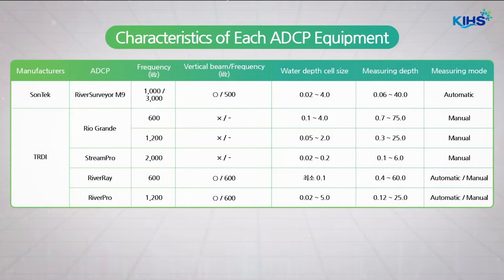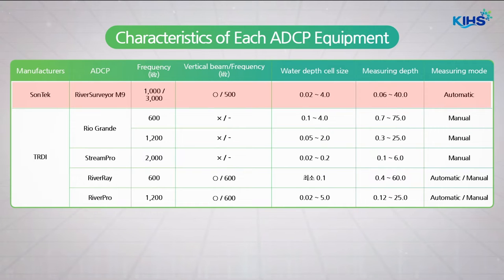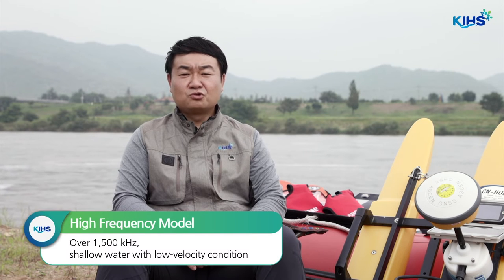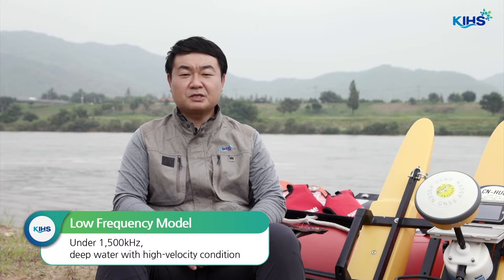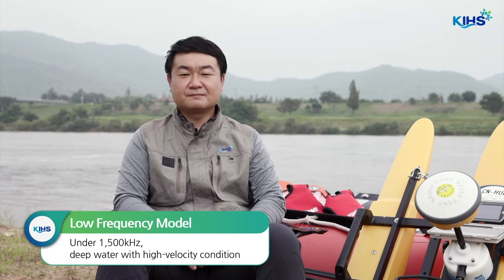Generally, the baseline that divides high-frequency and low-frequency is 1500 kHz. Recently, multi-frequency models such as the M9 are widely used. High-frequency models are appropriate for shallow water with low-flow conditions, while low-frequency models are suitable for deep water with high-flow conditions. Multi-frequency models can be used in all conditions.